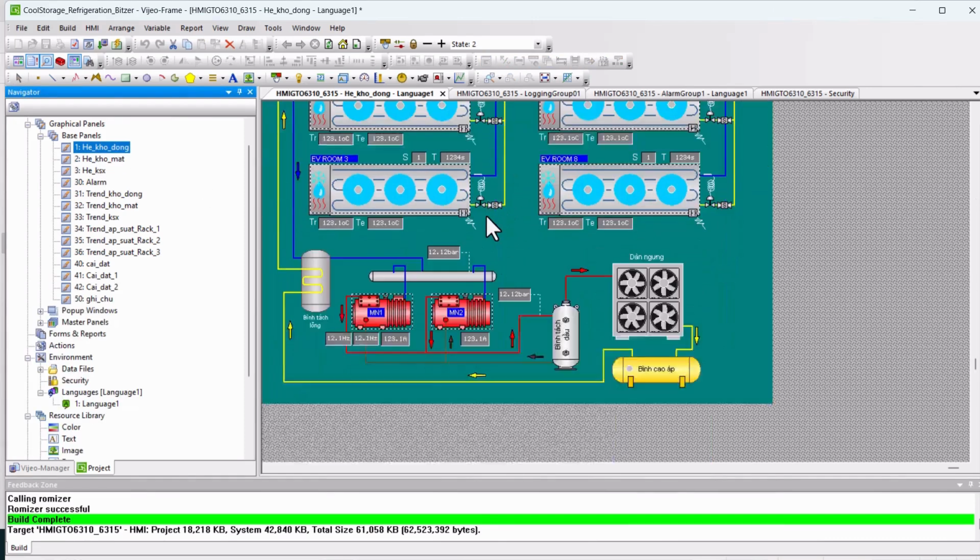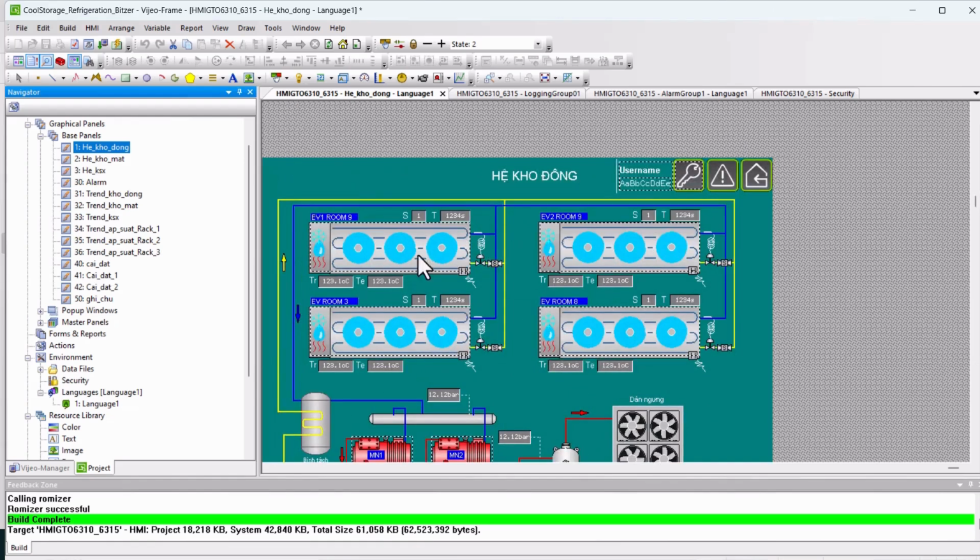Control the air cooler with the passive function: solenoid valve, refrigeration, defrost, and status of the fan, status of defrost, status of the refrigeration, status of fan, run, stop, valve, and step 1, step 2, step 3 to step 5 for defrost. This is the timer per step of defrost. And this is the room temperature and evaporation temperature.